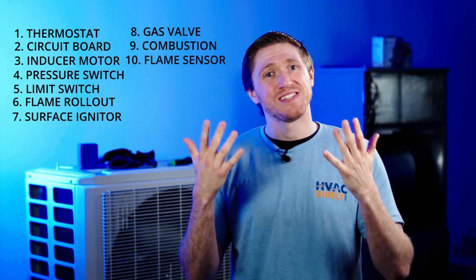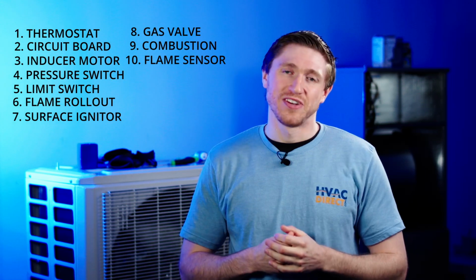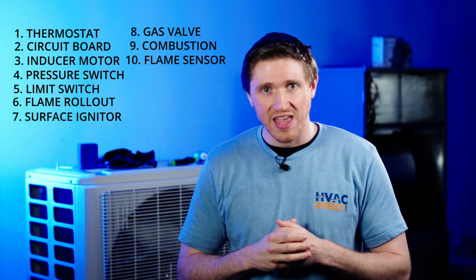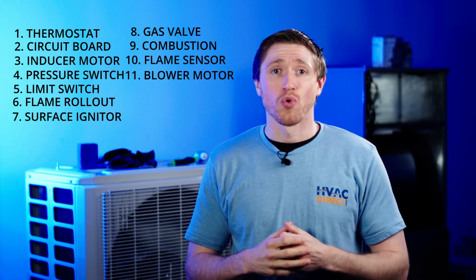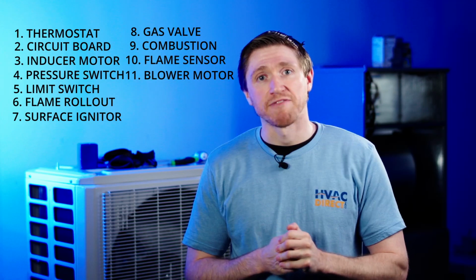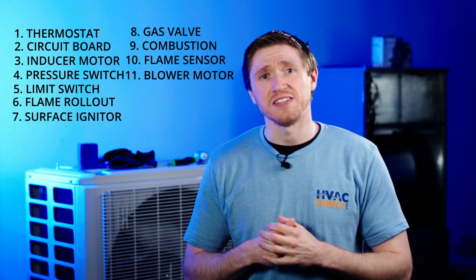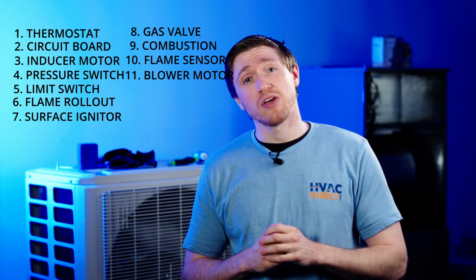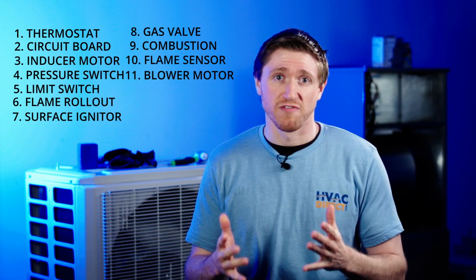And then number 10 is the flame sensor. The flame sensor is going to check to verify we actually have that flame. And then the 11th thing to make sure is that your blower motor does come on after typically about a 30 to 60 second delay, but keep in mind it could be longer depending on the settings of your furnace. I'll tell you right now, whenever your furnace is not working, you don't have heat, or you're blowing cold air, it's most likely going to be one of those 11 things that's causing the problem.